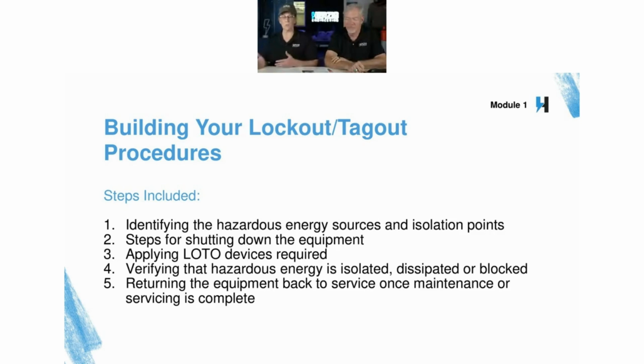In returning back to service, you're going to verify that all tools have been removed and that nobody is in a hazard zone—everybody is moved out of harm's way. If equipment involves movement, sudden movements can occur when you start it up, so you want to make sure people are out of the way. Communicate that the equipment is going to be returned to service, make sure it's ready to do so, and then remove those locks.